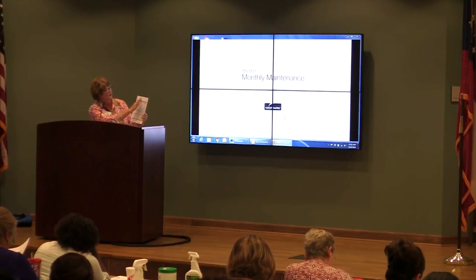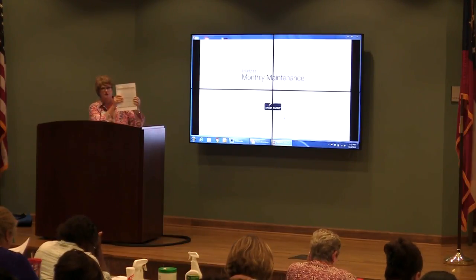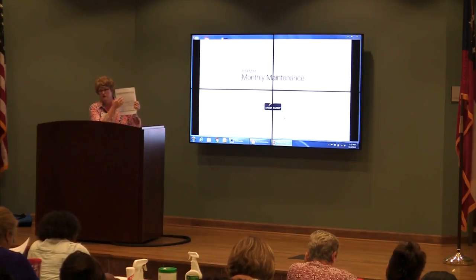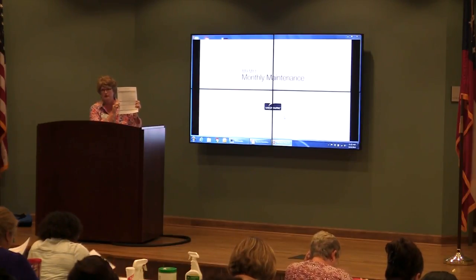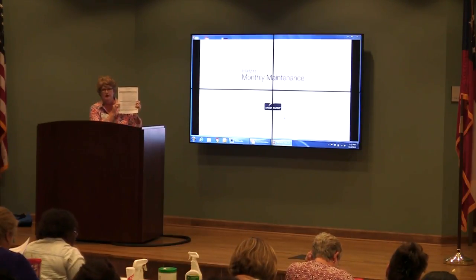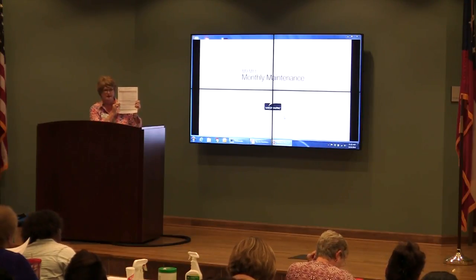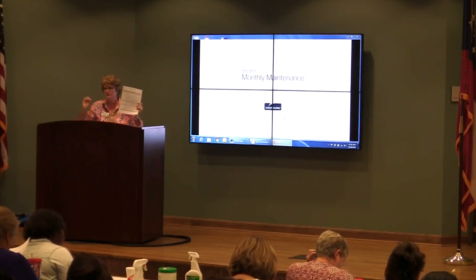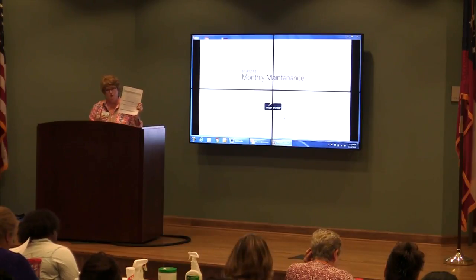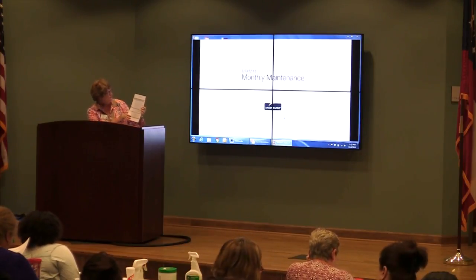It will also have your date at the top. You'll have a sheet for each month. And I want you to fill in the date that you do the monthly cleaning, which is every 28 days. Your autoclave will automatically tell you when it's time to be cleaned. It'll say monthly maintenance needed. That's when you do your monthly maintenance.